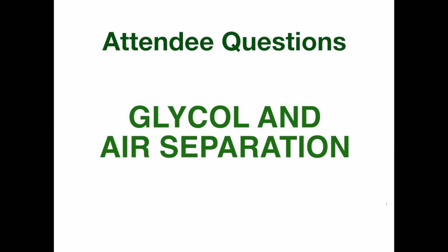Yeah, good point. I think a good bottom line to that, Mark, and everything you said was excellent, is it just takes more time to get air out of glycol. With a Discal, you put it on the system, and by the end of the job, at the end of the day, you've got all the air out. It's 100% air-free and quiet. It could take a couple of days to get it out of the glycol, certainly raising the temperature helps, and that fluid's just a tricky fluid for a lot of different reasons. Number one, glycol tends to leak out of a lot of threaded connections and stuff. The only good thing about it is it doesn't freeze, I suppose.